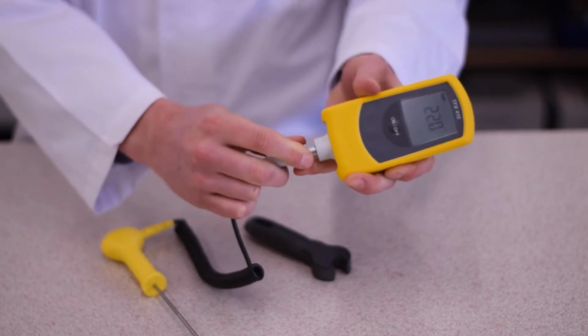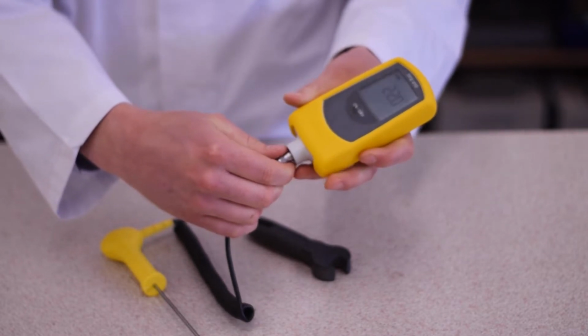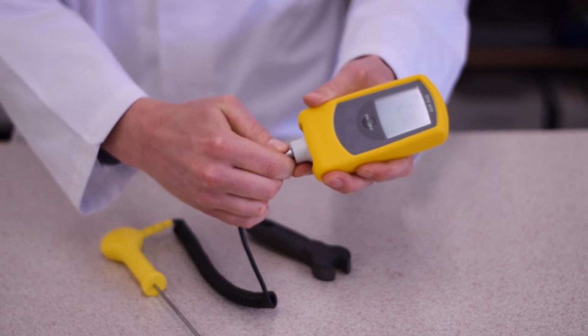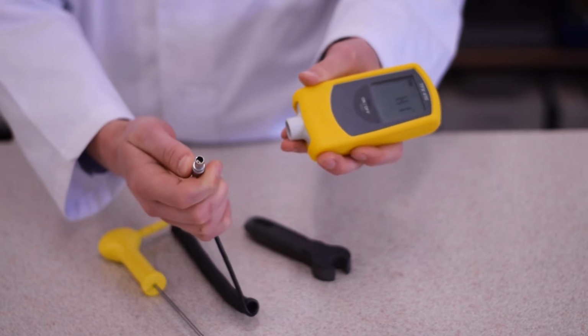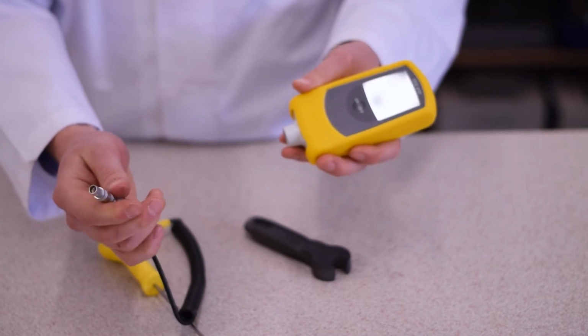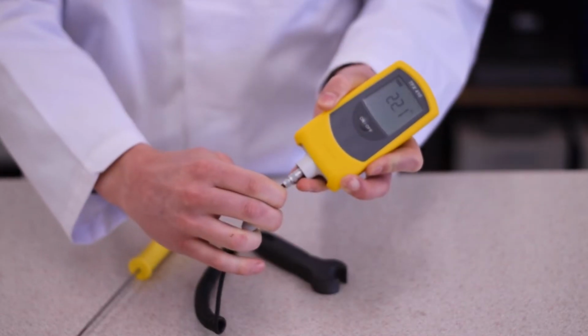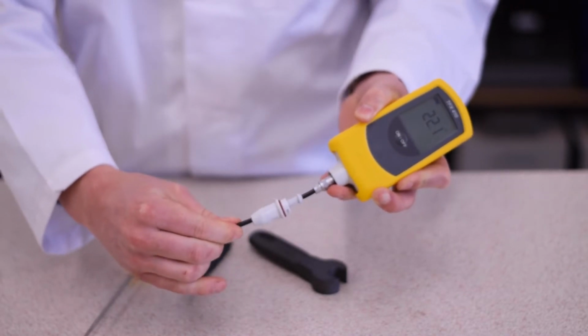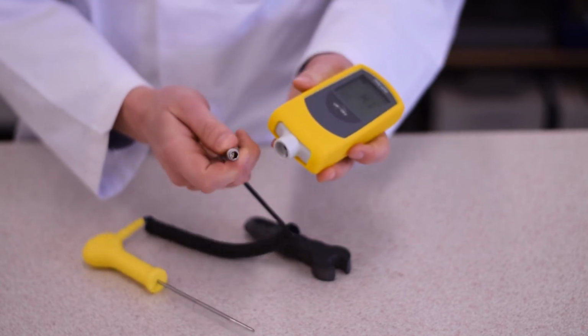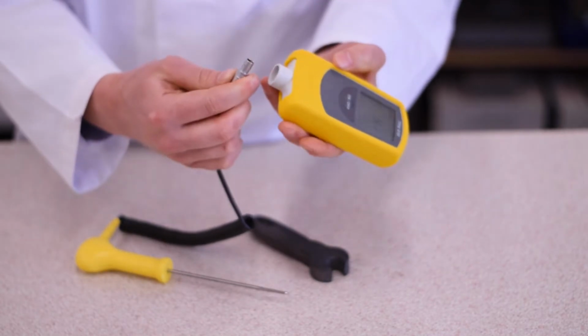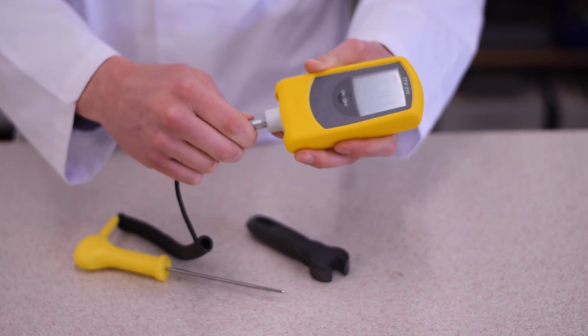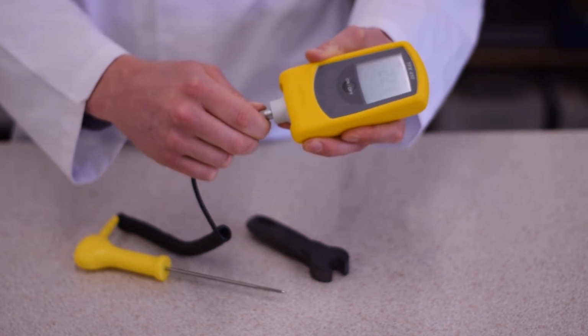Slide the cap down the wire about 2 centimeters and carefully pull out the plug-in connector away from the unit without twisting. Do not pull on the probe cable to remove the probe from the unit. When attaching a new probe, ensure that the pins in the metal LEMO connector are correctly aligned with the pins at the base of the thermometer unit. Push the connector towards the unit until you feel a click.